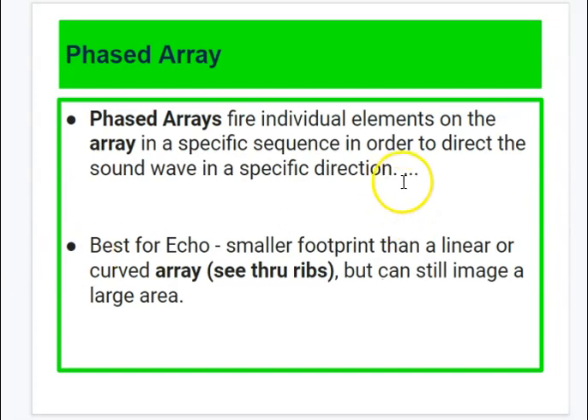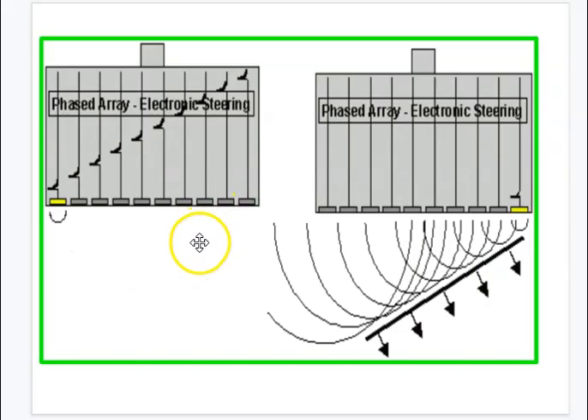Phased array transducers, as it says here, fire individual elements on the array in a specific sequence in order to direct the sound waves in a particular pattern. And this is best for echo because it has a very small footprint, which we've discussed in class, and it can still manage to see a large area. If you watch a phased array transducer, essentially it's firing these elements in a row here. Bing, bing, bing, bing. These are all coming down. So it can fire across and fire back this way. It's going to swing through the image like that. And this is happening, of course, a million times per second.